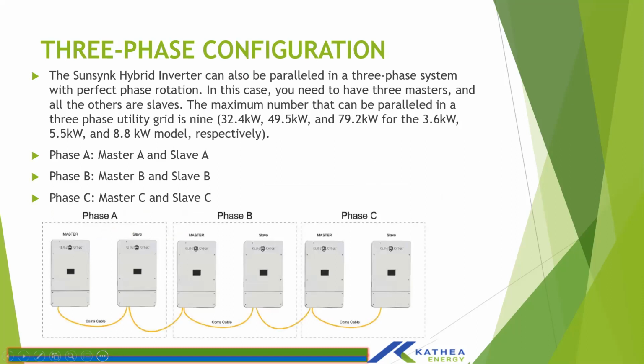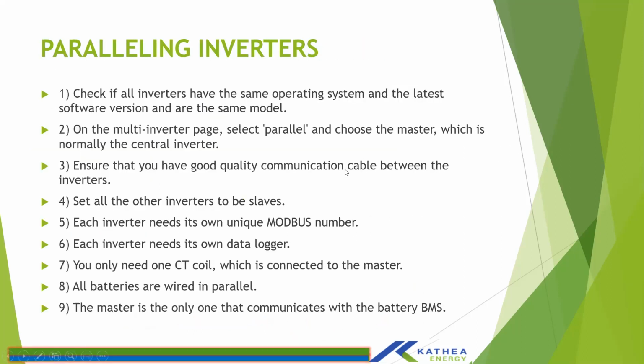And then on a three-phase configuration, you can connect up to a maximum of 9 inverters. Basically, you can connect 3 inverters in a phase, right? So you can go up to 9 inverters with 3 inverters on each phase. It means you can go up to 49.5 kilowatt for a 5.5, and up to 79.2 kilowatt for an 8.8 kilowatt system. And then on the settings, you are now setting for a three-phase system.